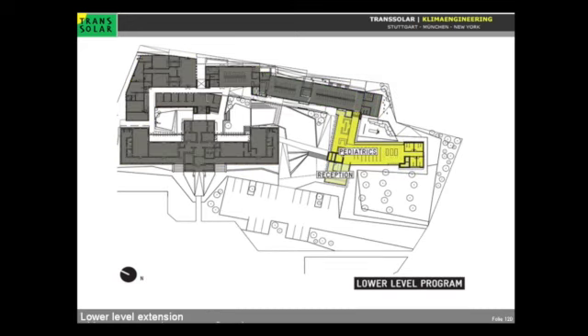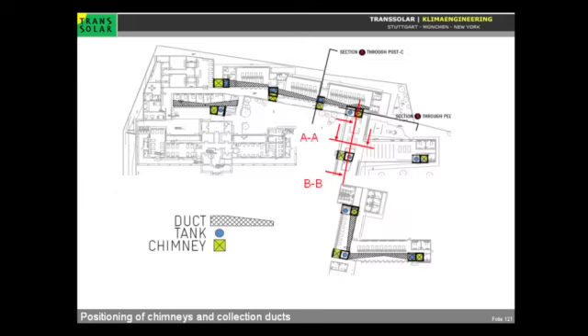One point is that the site is stepping down, and they are introducing a second level, which made it a bit more complicated, because doing natural ventilation with a solar chimney on a second level becomes tricky. So this is now the layout of all the chimneys, and they were quite astonished when I sized them. I sized the chimneys for low velocities, because if you look back in literature, old hospitals had air changes of 30 to 50 per hour.